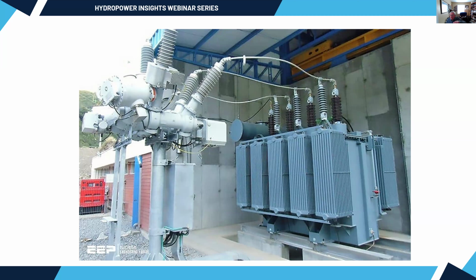You use a series of transformers to get the voltage up to a transmission level. Transmission voltages are anywhere from 69,000 volts to 765,000 volts. Actually, some are close to a million volts these days. But that's what you need to move energy long distances and minimize the loss.